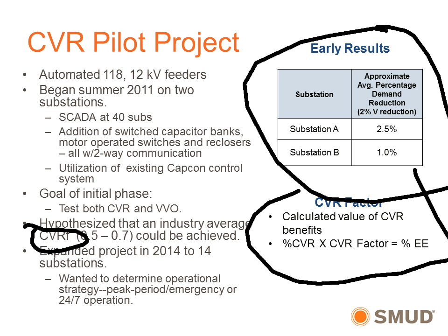Big deal, what's a CVR factor? On the right-hand side you can see it's basically a calculated value. You take your CVR factor, multiply it by the percent voltage reduction, and you get the answer. So if I have a CVR factor of 1 and do a 2% voltage reduction, I'm going to get a 2% energy savings.